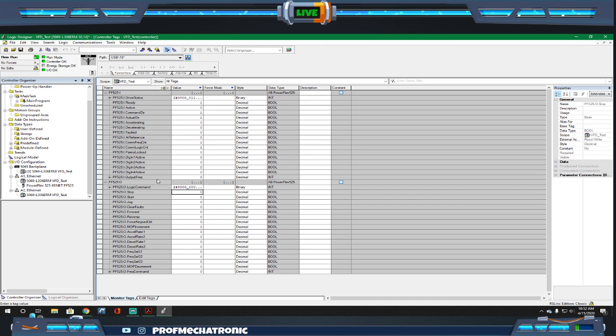We could actually command specific output frequencies, right? So if I say, listen, I want you to run at 50 hertz, I could put a value of 5,000 in there because this actual value of frequency command is done in 0.01 of a hertz. So now if I issue that start command, we're able to see the output frequency start to speed up. You shut the start command off, and you see the output frequency still is turning on until we issue the stop command. And now you can see the deceleration curve of the drive actually slowing down until it actually comes to a stop.